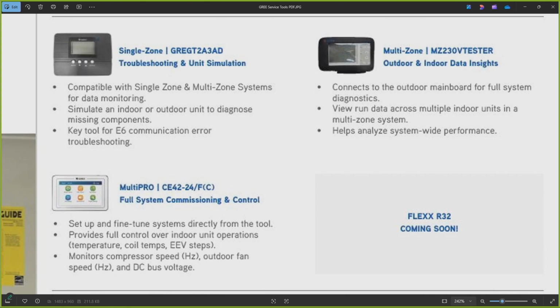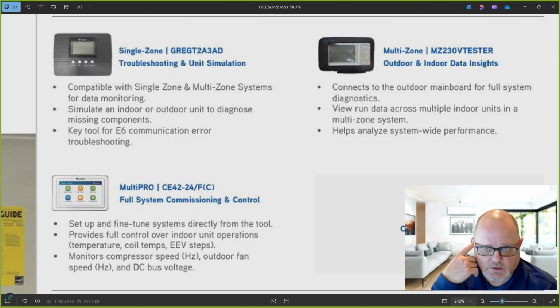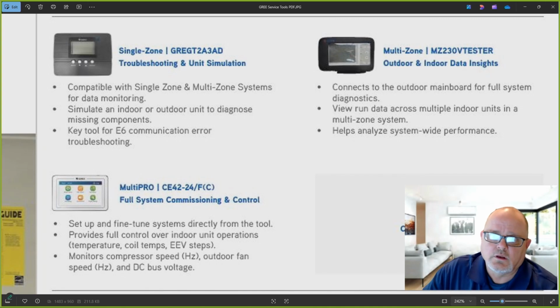The other thing I really like is that it will simulate. So when you have an E6 error code, you can hook up to the outdoor unit and simulate the indoor unit to see if you still get an E6. You can also hook up just to the indoor unit and simulate the outdoor to see if you get an E6 error code. So you can quickly determine whether the problem's in the outdoor unit or the indoor unit and know where to go from there.